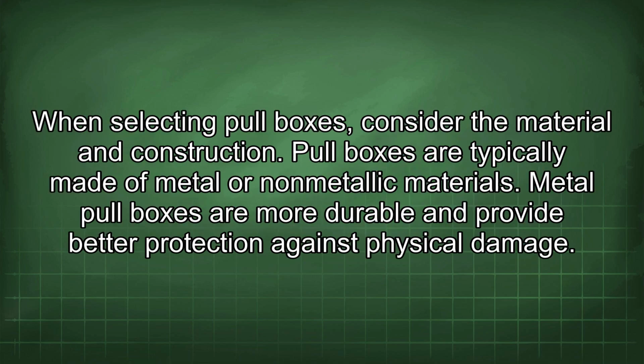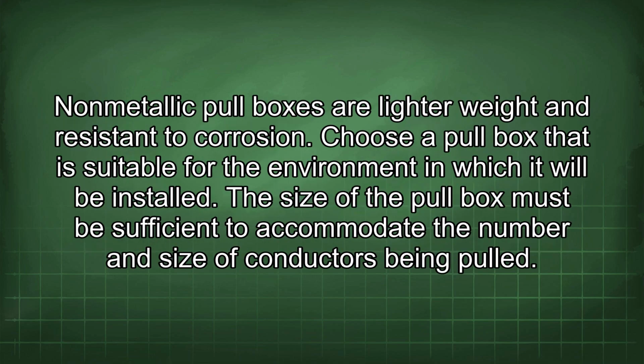When selecting pull boxes, consider the material and construction. Pull boxes are typically made of metal or non-metallic materials. Metal pull boxes are more durable and provide better protection against physical damage. Non-metallic pull boxes are lighter weight and resistant to corrosion. Choose a pull box that is suitable for the environment in which it will be installed.